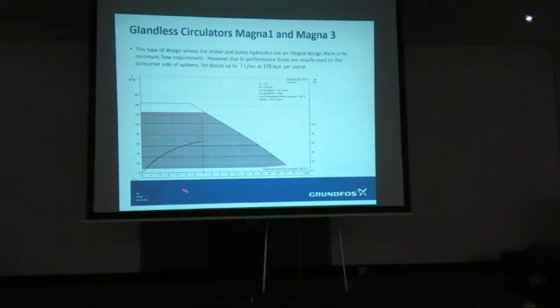To me, 5, 6, 7, 8 litres a second, up to 100 kPa maybe, that's where it used to be when I started in the industry. But you are finding 150, 200 kPa nowadays because of long runs of pipework and so forth. If you can get them down to this area, not a problem. You have to worry about minimum flows. You still need a minimum flow to keep all that kind of stuff.